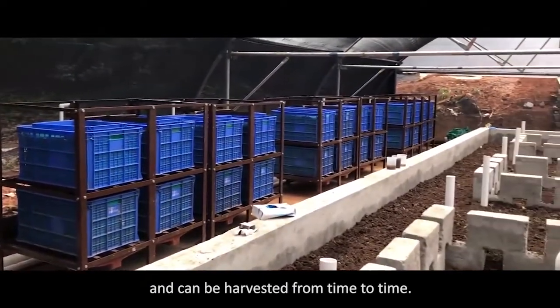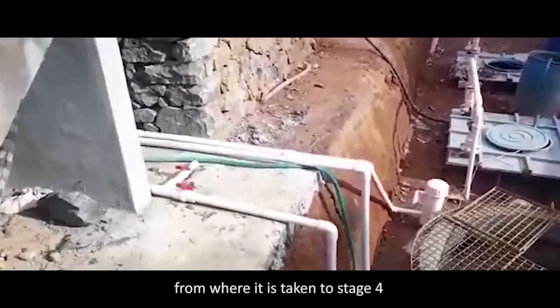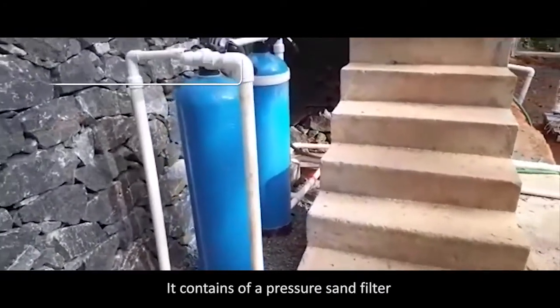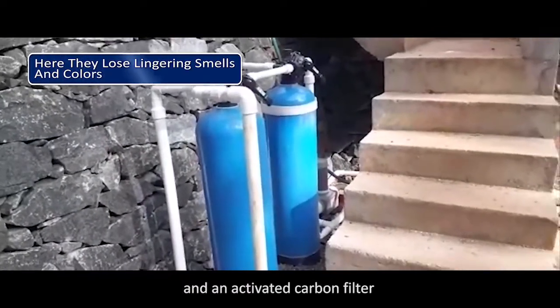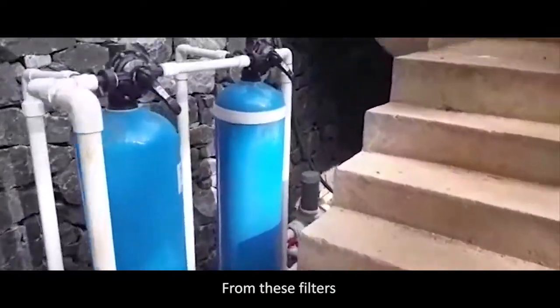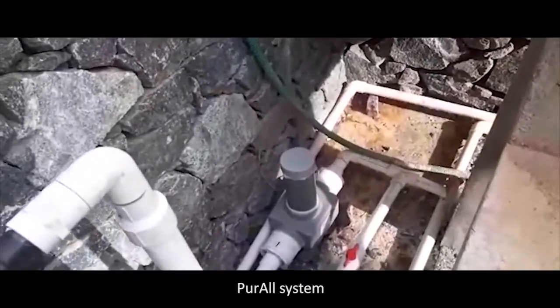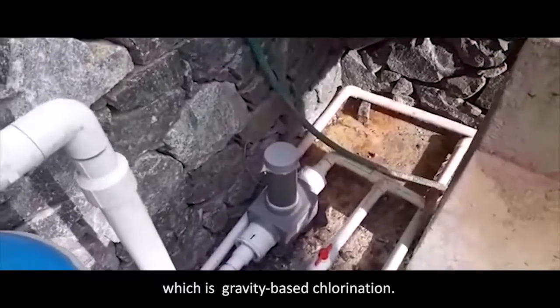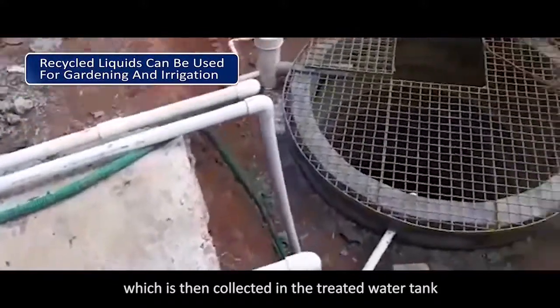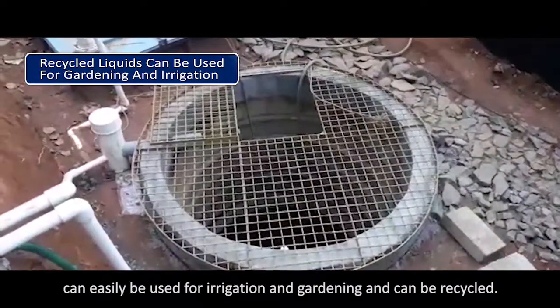The vermicompost formed during the process of waste digestion is collected inside the inner blue crates and can be harvested from time to time. The effluent from stage 3 is collected into another underground tank, from where it is taken to stage 4, the polishing stage. It contains a pressure sand filter and an activated carbon filter which helps remove the colour. From these filters, it is passed through a chlorination device called the PurAll system, which is a gravity-based chlorination system. It disinfects the effluent, which is then collected in the treated water tank and can easily be used for irrigation and gardening.